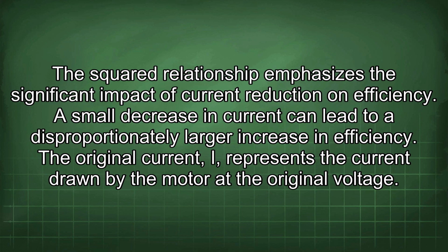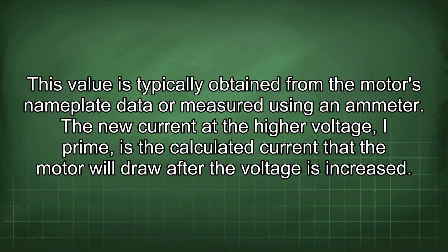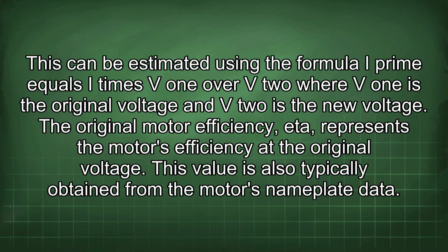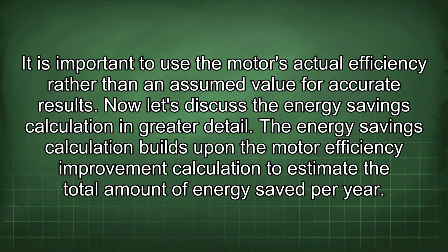The original current, I, represents the current drawn by the motor at the original voltage. This value is typically obtained from the motor's nameplate data or measured using an ammeter. The new current at the higher voltage, I prime, is the calculated current the motor will draw after the voltage is increased. This can be estimated using the formula I prime equals I times V1 over V2, where V1 is the original voltage and V2 is the new voltage. The original motor efficiency, eta, represents the motor's efficiency at the original voltage. This value is also typically obtained from the motor's nameplate data. It is important to use the motor's actual efficiency rather than an assumed value for accurate results.